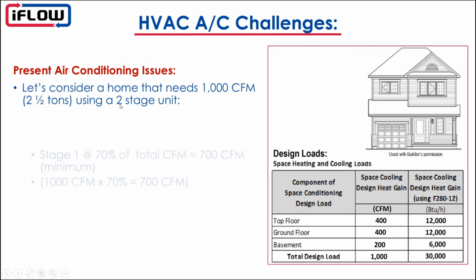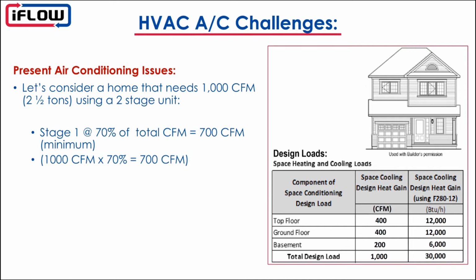Let's consider a two-stage unit. If we have a two-stage unit, stage 1 will come on at 70%. So our maximum CFM at stage 2 would be 1,000 CFM, and our stage 1 would be 70% of that, so 700 CFM.